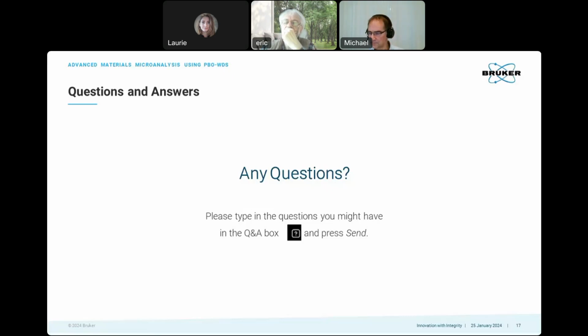Thank you. Maybe another question for Michel. Why is your system more efficient on low energies? Like I showed, the system has a very high solid angle, and that is due to the optic, the parallel beam optic, and especially this grazing incidence optic with the metal cones, so it captures a maximum of X-rays. So that's one point, the optic itself and the optic close to the sample. And the other effect is also given by the diffractor crystal or the multi-layer analyzer.